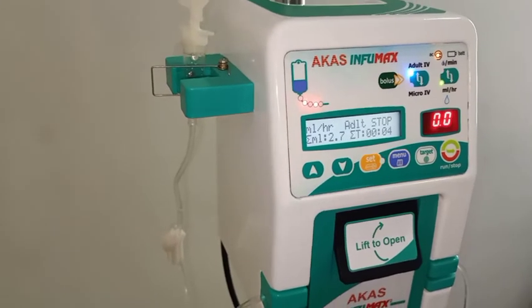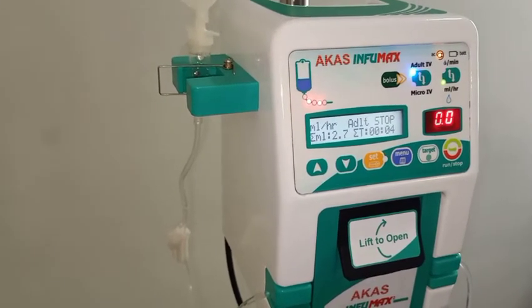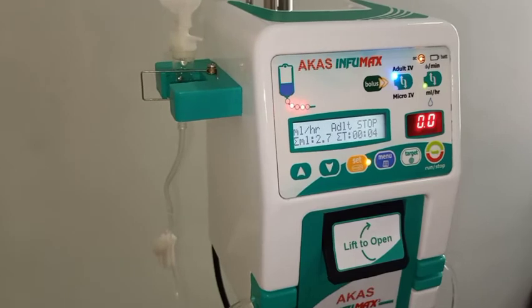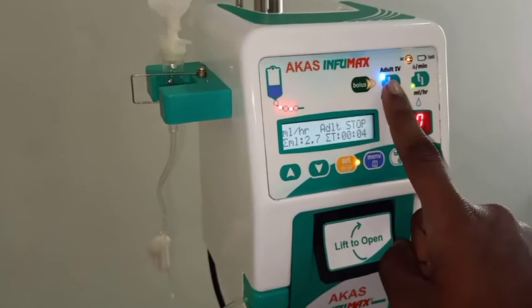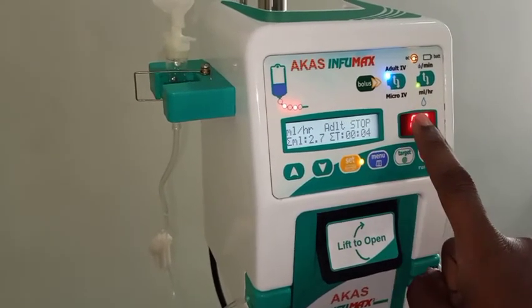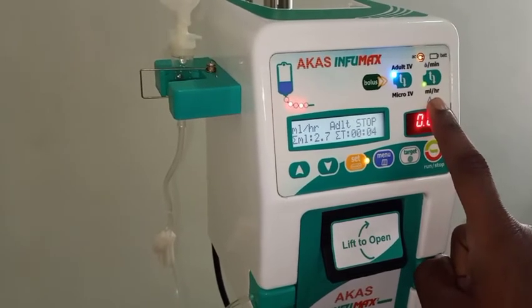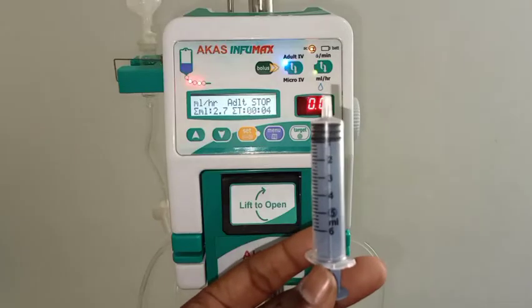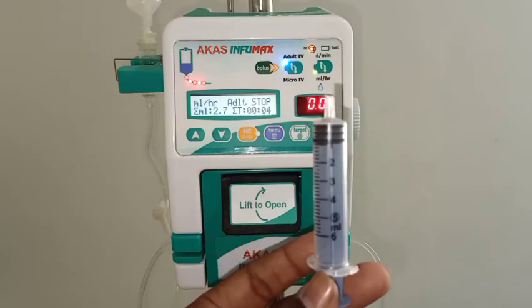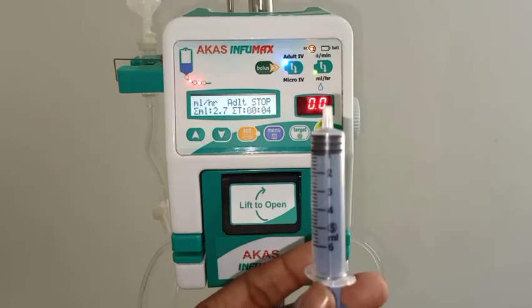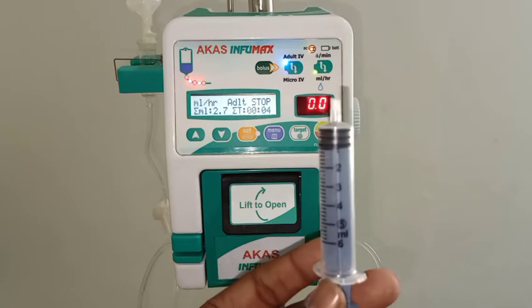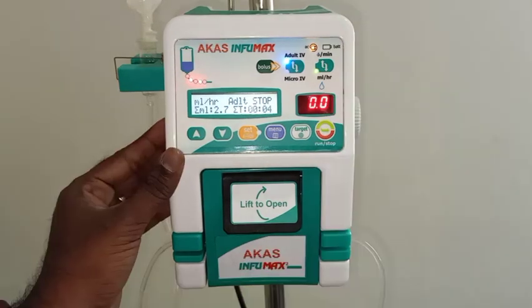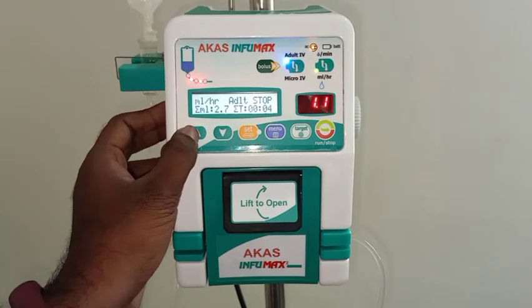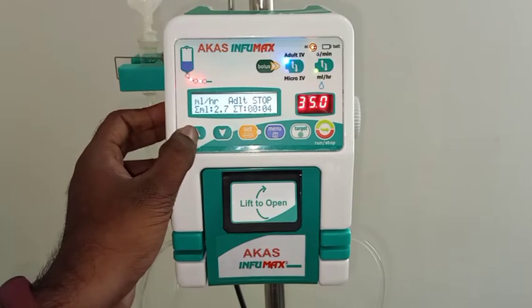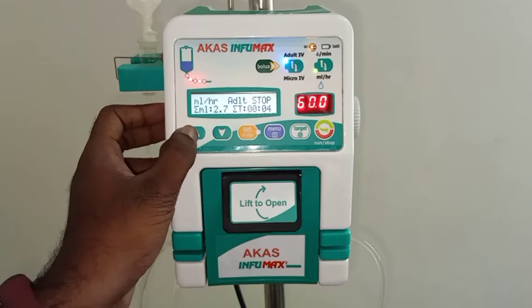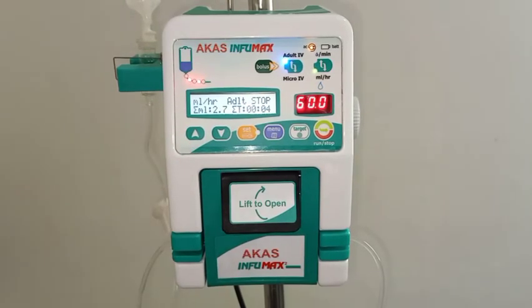In this video we are going to see about adult IVTube calibration. I have taken the adult IVTube and kept adult in the machine, and we need to change it to ml per hour. We need to take the 5 ml empty syringe and we have to keep the flow rate of 60 ml per hour. I have kept the flow rate of 60 ml per hour. Now the flow rate is set.